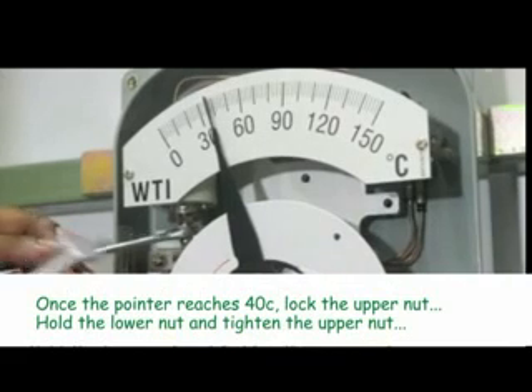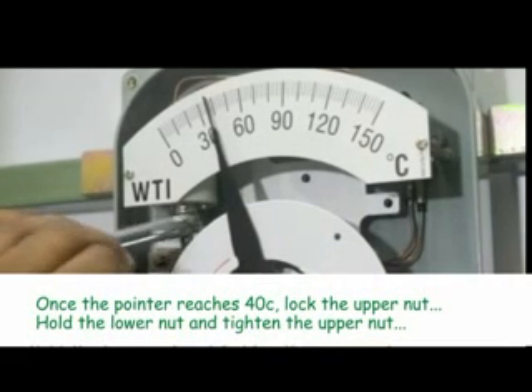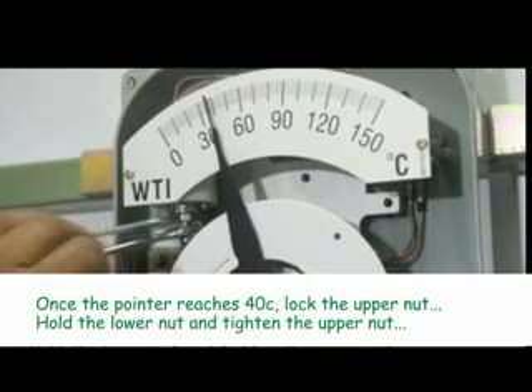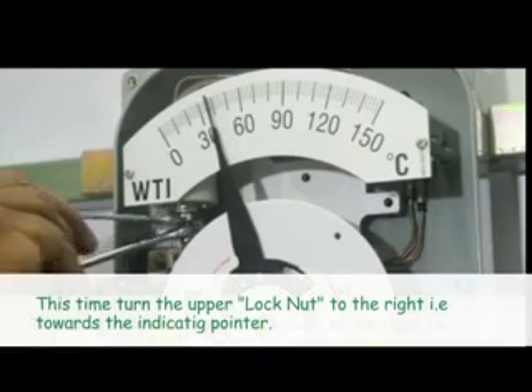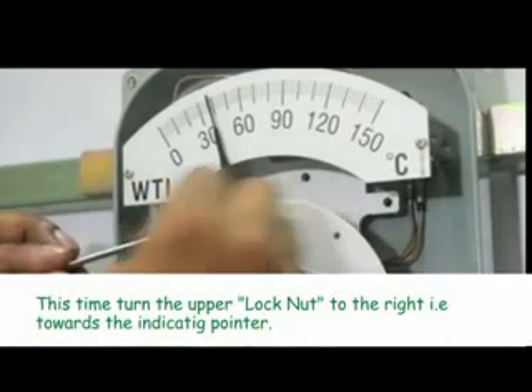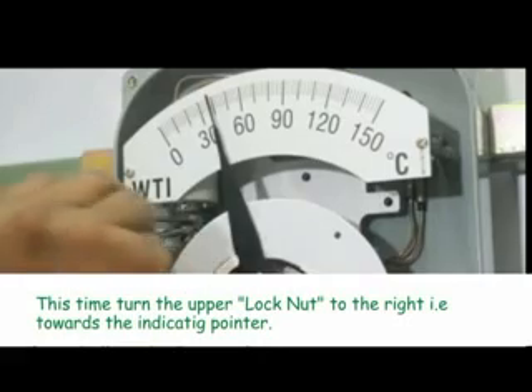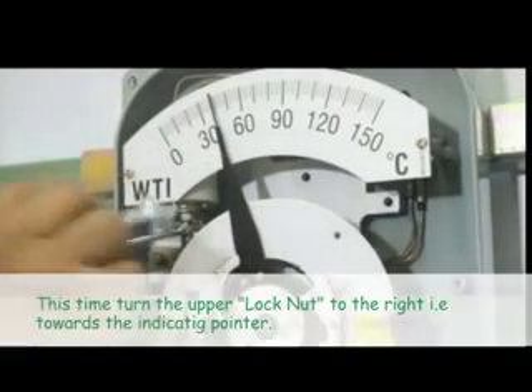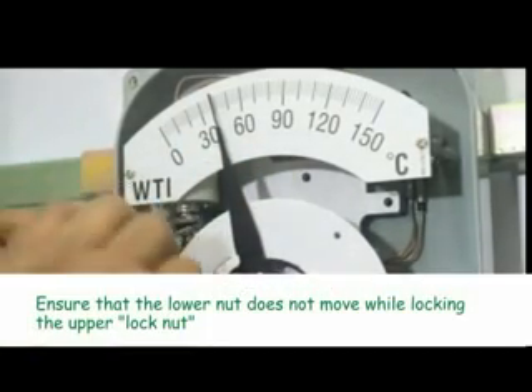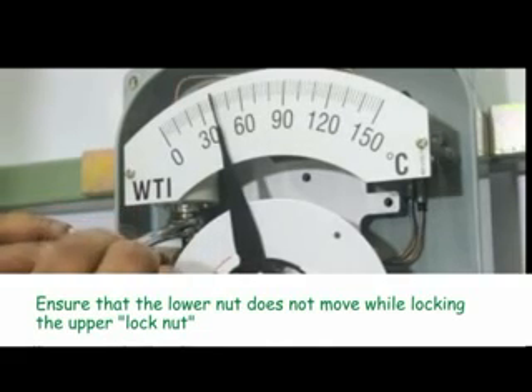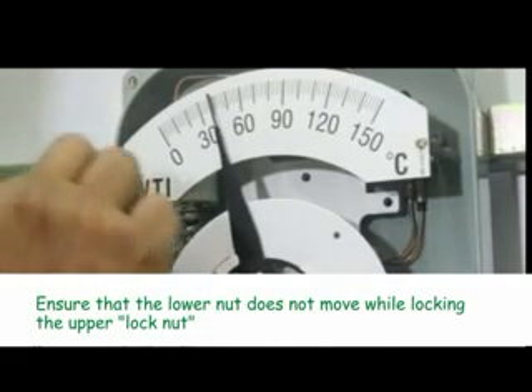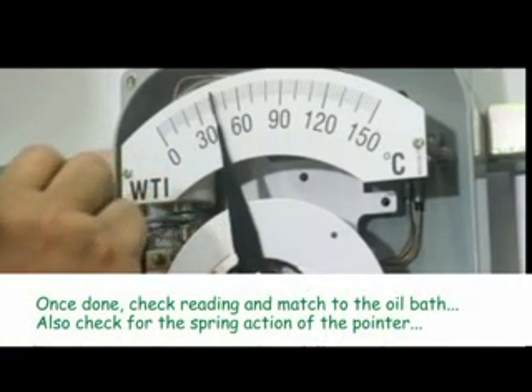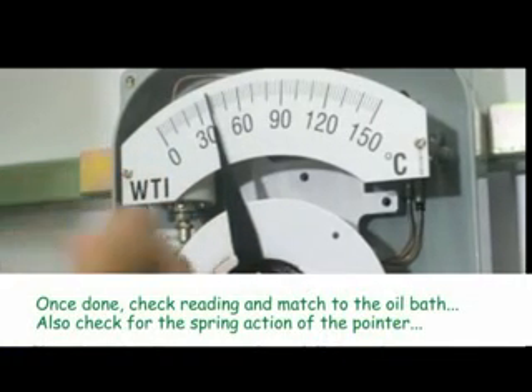Once the pointer reaches 40 degrees centigrade, lock the upper nut: hold the lower nut and tighten the upper nut. This time, turn the upper lock nut to the right, that is, towards the indicating pointer. Ensure that the lower nut does not move while locking the upper lock nut. Once done, check the reading and match it to the oil bath. Also check for the spring action of the pointer.